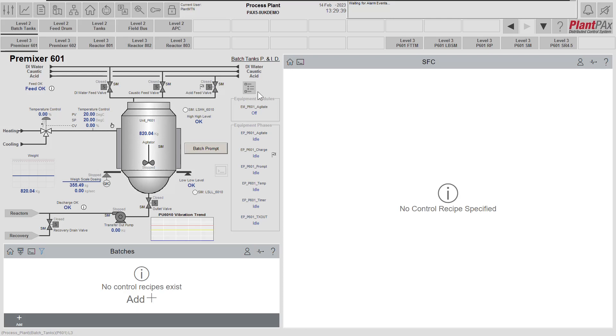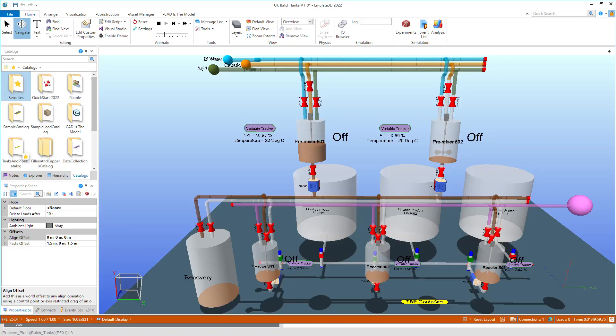We're using another Rockwell Automation product to simulate the batch tank area that this pre-mixer is a member of, and that is Emulate 3D. In Emulate 3D we've built a model of our batch tank area using the tanks and pipes catalog. Emulate 3D will simulate the process without having to put any additional logic in to do that specifically, and we've connected Emulate 3D to our PlantPAx process controller using the I/O mapping capability in Emulate 3D.